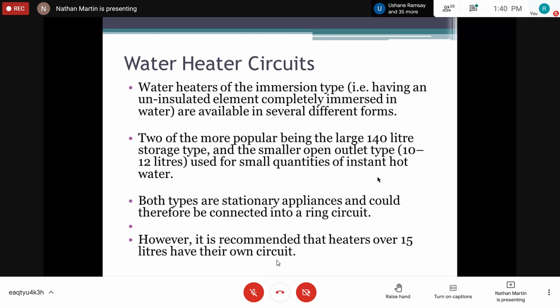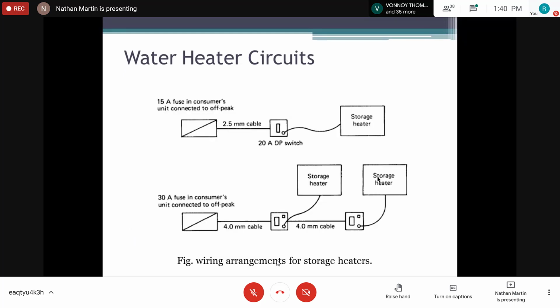They must have their own circuits, right? When we talk about their own circuit, it means it must have a single breaker and it must control only that water heater alone, right? So I'll give you an example of the type of connections that can be used for water heaters, right?